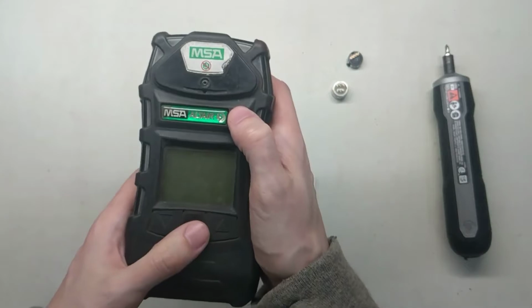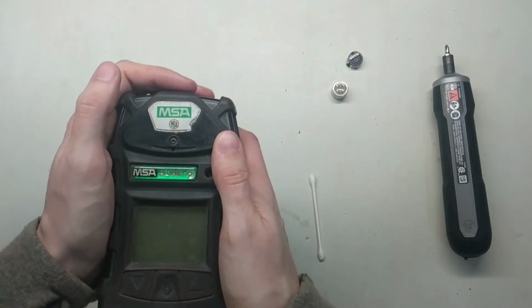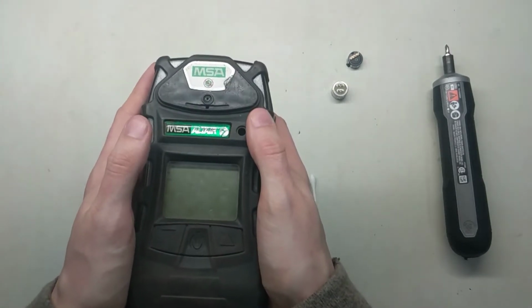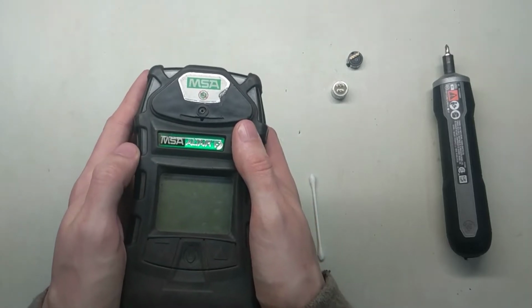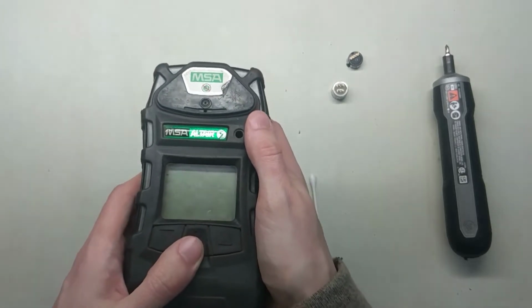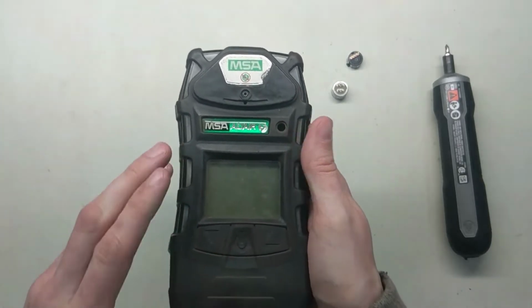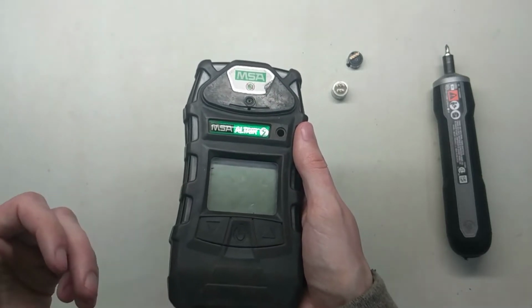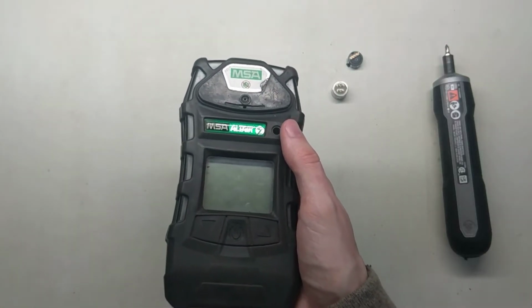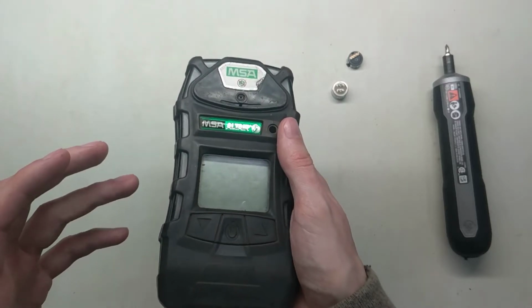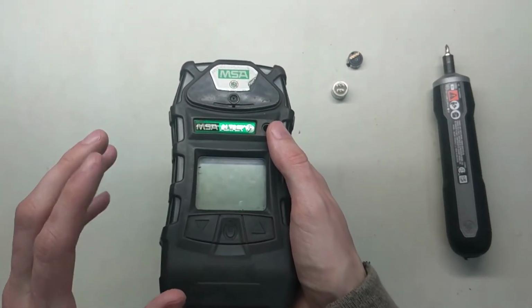One thing you're going to want to do, now that we've installed a new oxygen sensor, is give it about an hour of sitting in there before we do anything with it. So you can turn it on and check it, but don't bother zeroing it or calibrating it. Just have it installed in there and let it sit. What happens is the oxygen sensor needs to sit in room air for a little while so it starts to acclimate to being out of the packaging.